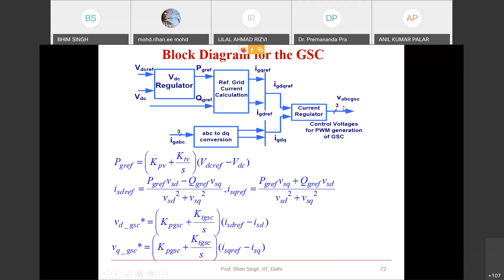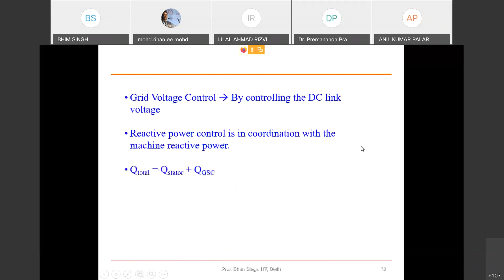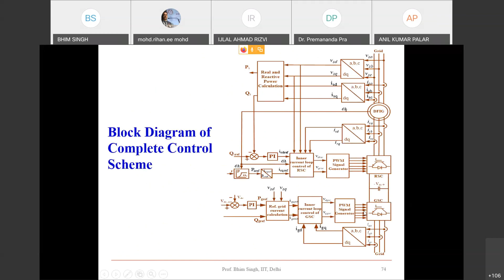And then again you have DQ currents: you sense the current, which you have converted into DQ, then a current controller again on DC quantities. That is vector control, and then you get the voltage here, convert the references to 3-phase voltage, and have pulse width modulation control. So 4 PI controllers here, 4 PI controllers there, so you have 8 PI controllers virtually in this DFIG as a benchmark. And this is typically the control block diagram which I mentioned, of the rotor side converter and grid side converter. You sense the rotor current, you sense the grid current, the converter current on the grid side, and then control both with several PI controllers, which I already mentioned.